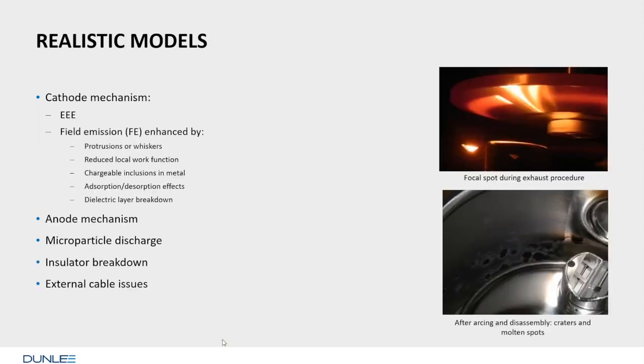Other causes? Yes, there are. One of the best models, I think, is the EEE model, the explosive electron emission model. You see here a tube in operation, a cathode here. The cathode is on. The electron beam hits the focal spot. It's a rectangular focal spot on the focal spot track. And between these two electrodes, we have 150 kilovolts. That is pretty much for this little distance here. And if the tube does not work too well, if the process is not good or the surfaces are not good, then you end up with something which you see here to the right.